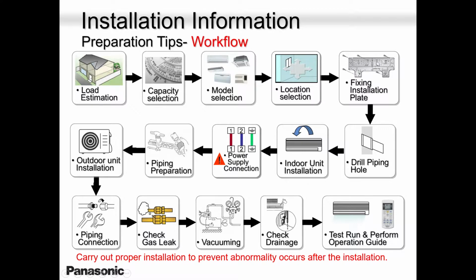Then comes the back plate. You know, the back plate is so important. Why is it important? It's because it's protecting the alignment of the blower wheel. If this back plate is not smooth, straight, and square, you will lose the blower motor, maybe the blower wheel also, after less than nine months. So please, this back plate sounds very easy to install, but if it is installed incorrectly or with fewer screws and plugs, you will have problems with the motor.